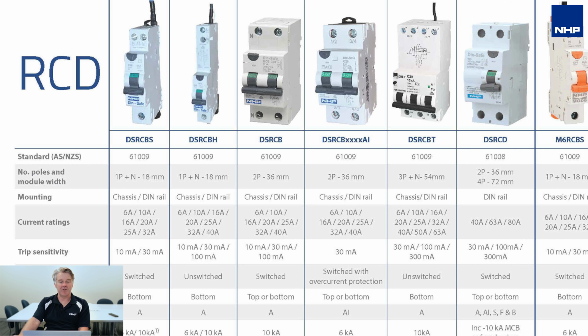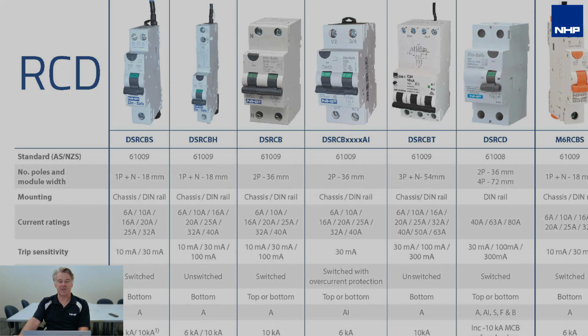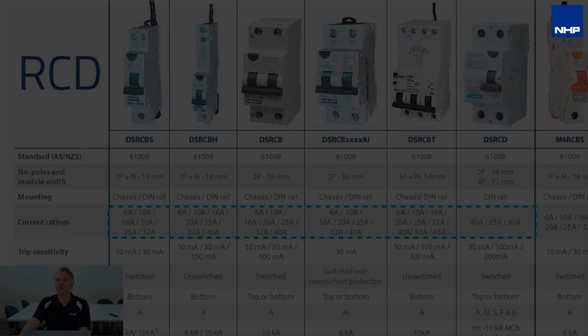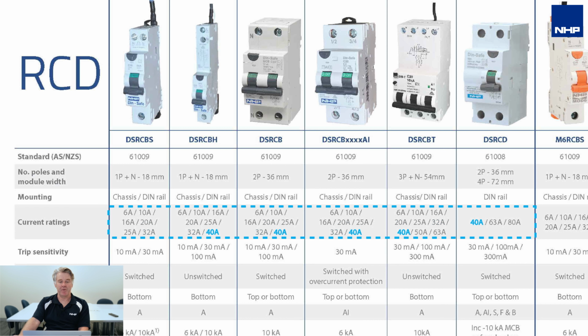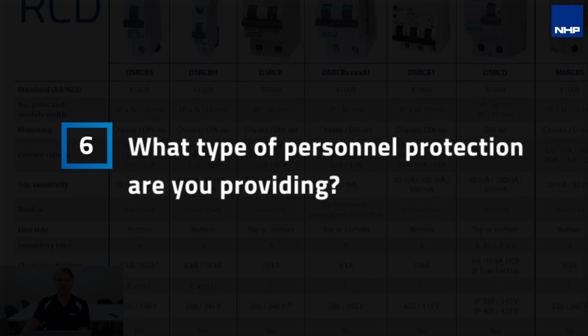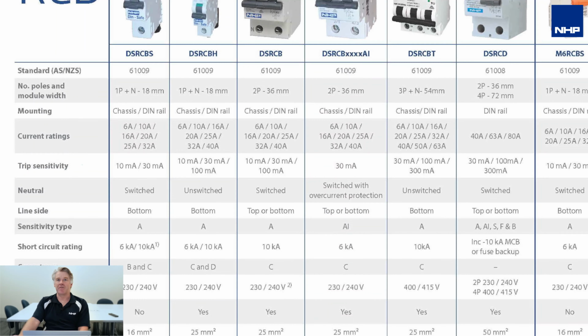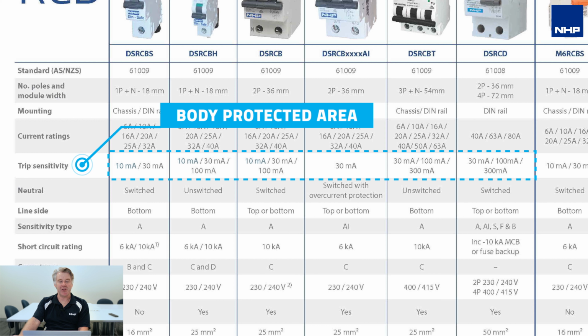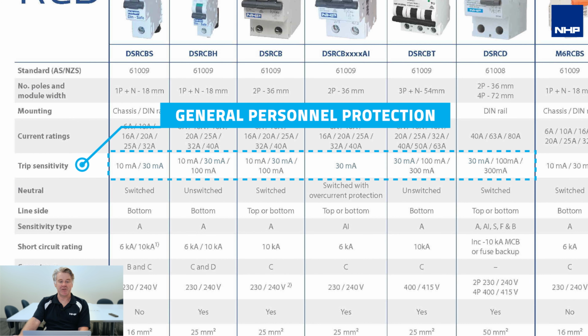So once you've chosen the form and fit of the RCD device you'd like, the next one is choosing the current rating. Do you need it to go up to 20 amps, up to 32 amps, 40 amps, or 63 amps? So depending on what current rating, it may limit the choices you have here. Then of course, the type of personnel protection you're trying to provide. Is it for a body protected area where you may need a 10 milliamp device, as you can see along here, or 30 milliamp for general personnel protection, or if it's for equipment and plant protection, you may choose a 100 milliamp or a 300 milliamp device.